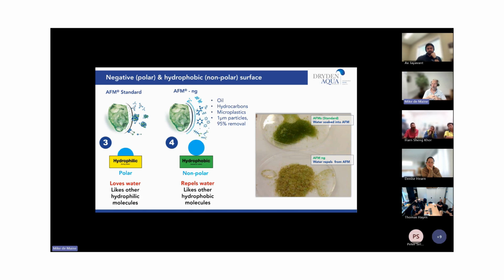So what ends up happening is because of the NG, the hydrophobicity, it holds onto a lot of air. That either needs a 24-hour soaking period for the excess air to be released off the AFM, or because our media is so clean, quite often we just tell the client to put it straight into filtration mode for 24 hours before you backwash it. If you do it normal like sand, you would install sand and then you would backwash it first, you will lose a lot of your media because of the media that's floating. A lot of the media will be floating initially. So it's got a slightly different installation capacity.